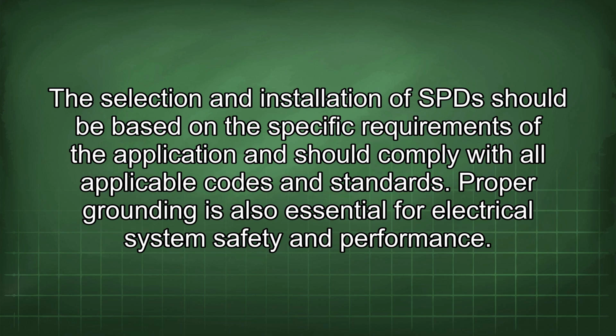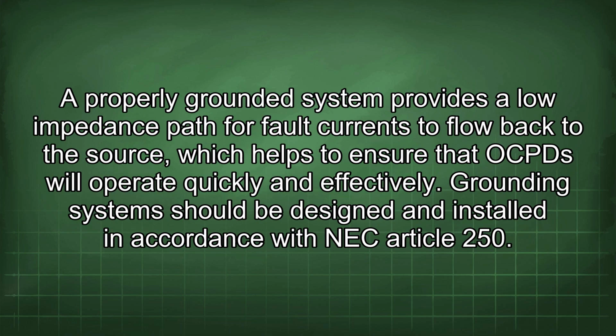Proper grounding is also essential for electrical system safety and performance. A properly grounded system provides a low impedance path for fault currents to flow back to the source, which helps to ensure that OCPDs will operate quickly and effectively. Grounding systems should be designed and installed in accordance with NEC Article 250.